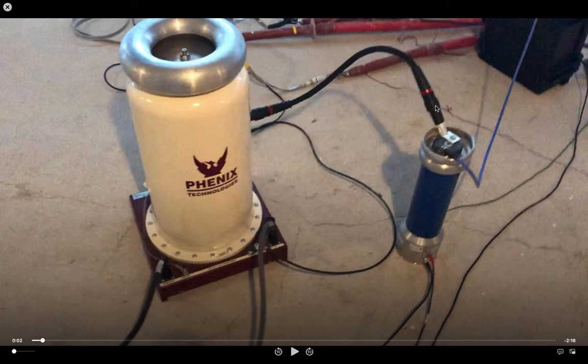Now this sensor here is called a capacitive divider. This sensor here has one input and it has two outputs. These two outputs - remember this is red color and this is black color - the red one is high frequency, which means through that output, by using this coaxial cable which is directly connected to the acquisition unit, we send a PD signal. That PD signal is received both from the source - the source definitely has a very low PD signal but it has some - and also PD from the cable which is connected in parallel.